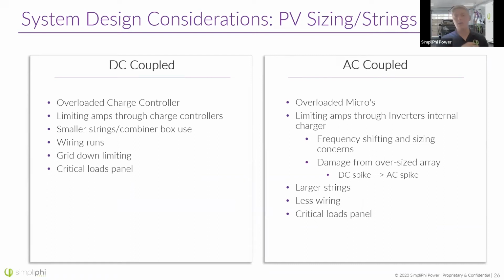Now, a lead acid battery bank, you overcharge it a little bit, the voltage rises a little bit, no problem. With a lithium battery bank, when it gets to the top of its charge cycle and it's full, a very small overcharging event can cause a very quick voltage spike. And this will not only affect the batteries and the inverter, but if it's bad enough, it can even pass on to the AC side, such as the appliances and the microinverters can see that AC voltage spike as well. So really, when you're designing an AC coupled project, sizing is much more key. You have to make sure that you're not overloading those micros and you're not overloading the battery bank and charging that faster than it can be charged as well.